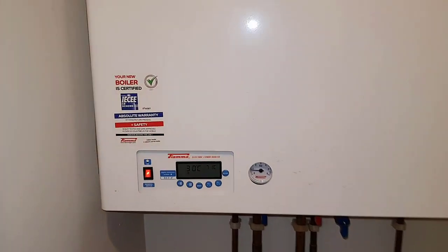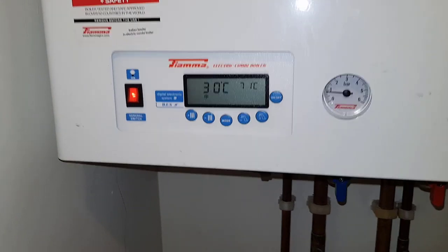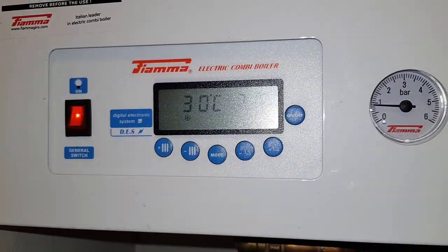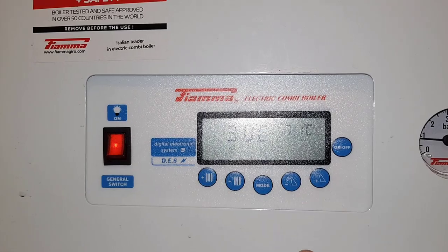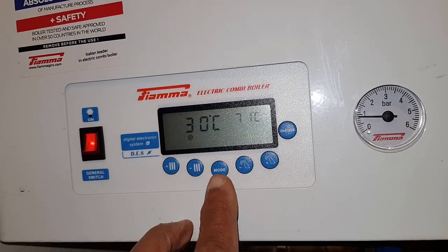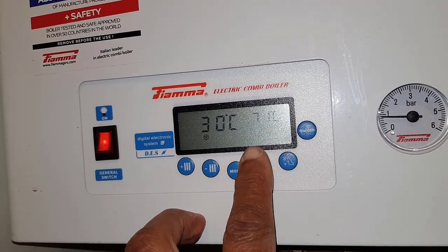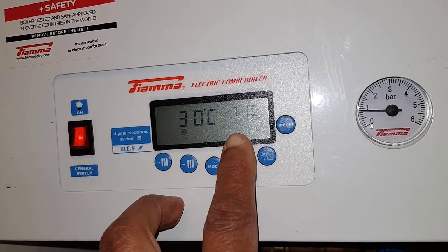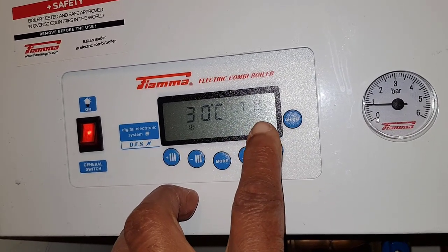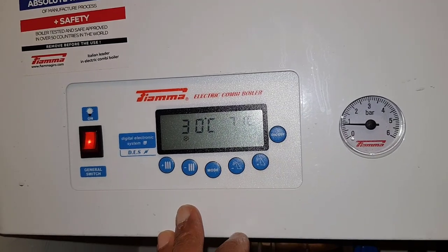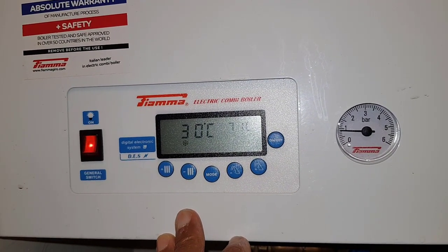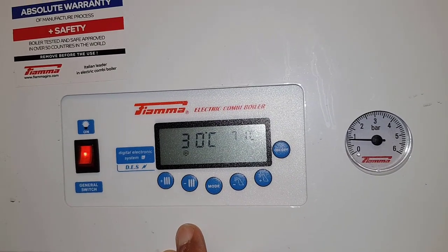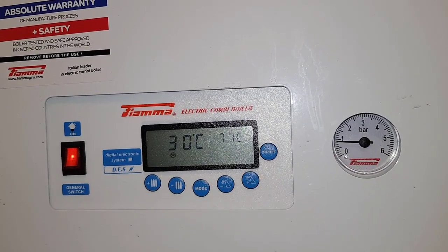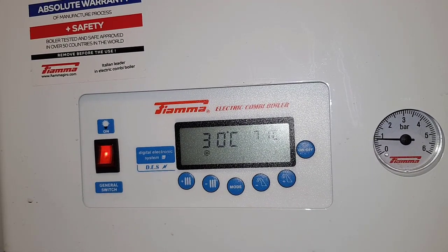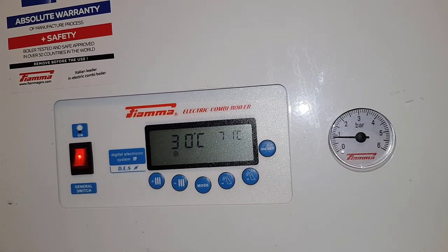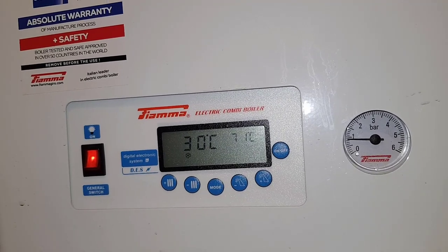Now I've just run the hot water, and I'm going to show this screen here. What should be happening is you should have a little hot water symbol flashing, and you should see some bars going across. You should also hear the pump running, but at the moment we're not getting any of that. So that's one problem we've got, and also, as I said, it's not turning off. So we're going to look into this problem first.